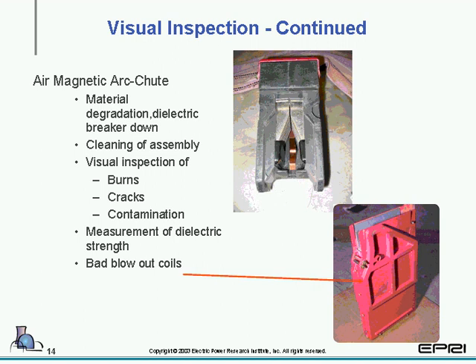Also, you may come across bad blowout coils. On larger design breakers, you may have coils that are used for magnetic draw to draw the arc up into the arc chute. These should also be tested. And typically, what you should see is less than 1 ohm.